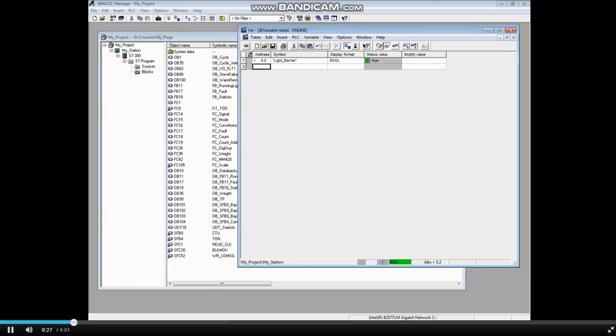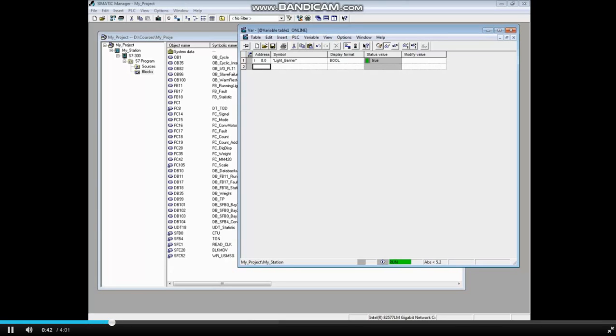Creating a variable table by using the Monitor Modify menu is particularly useful for a quick look at I/O. When you go to save though, the location does not necessarily default to your open project. It defaults to the first project in your list. Let's see how to create a variable table that is always associated with your project.